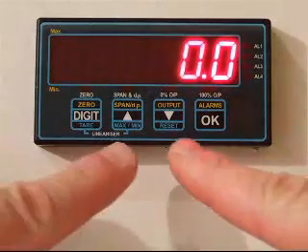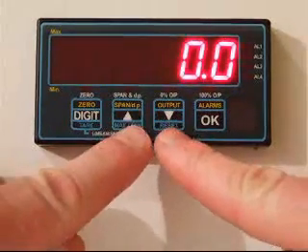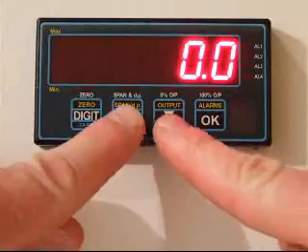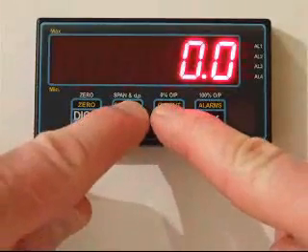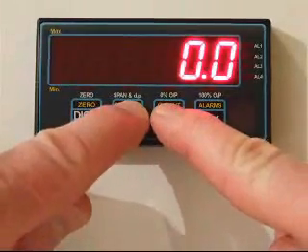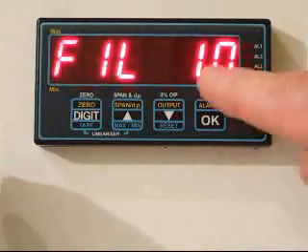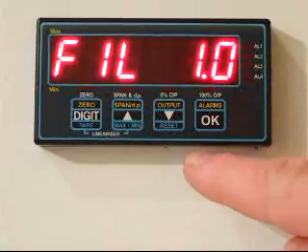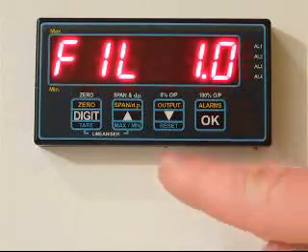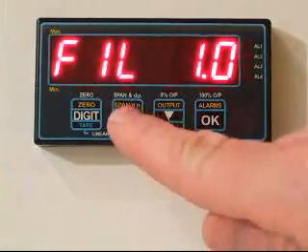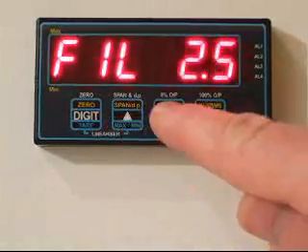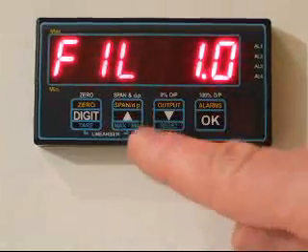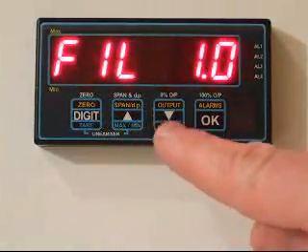You can access the filter variable by pressing the middle two buttons on the front panel for about three seconds. The display shows 'filter' with the time constant of the filter in seconds. You can increase or decrease this value using the up and down buttons.